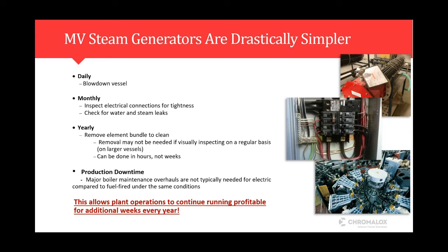Also on a yearly basis, remove the bundle and inspect for cleanliness to make sure there's not any buildup. But those types of checks can be done on the order of hours, not days or weeks like you see with any kind of larger failures that might happen on the fuel-fired side. So again, from the perspective of maintenance, these systems are much more simple. The failures you're going to see are typically on commodity parts like fuses, contactors, things that can be replaced very quickly. So the takeaway here is the electric system allows you to have a lower cost maintenance schedule, but also keep the system up and running more days and more weeks out of the year, which basically means higher profitability.